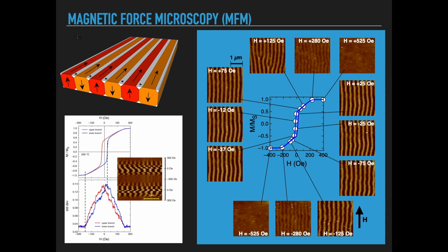When the magnetization of the sample has suitable characteristics, it is possible to do imaging with a magnetic force microscope not at constant magnetic field, but at varying magnetic field. The idea is that an image acquired by a magnetic force microscope is made of several different lines that normally reproduce the magnetic domain configuration over a certain field of view. However, it is possible to disable the scanning of the magnetic tip in one direction in order to repeat the scanning of the same line over and over again. If the applied magnetic field is synchronized with the scanning of the microscope, each line will be acquired at a different magnetic field value. This way, it is possible to study the evolution of the magnetization along that line in a single image for a given magnetic field history.